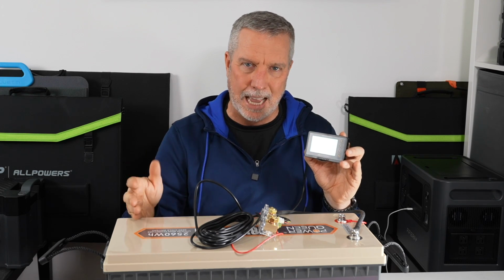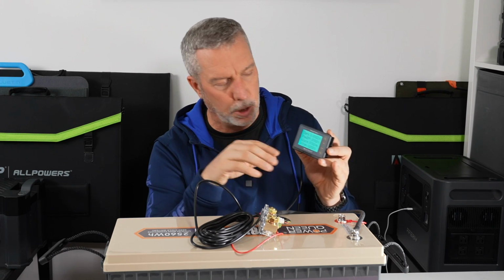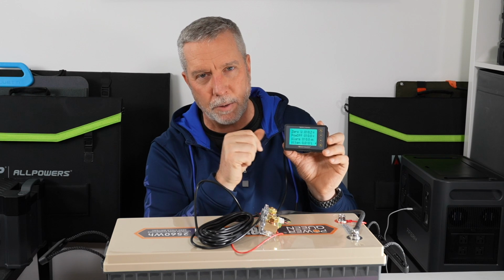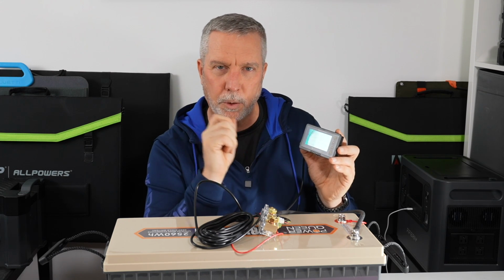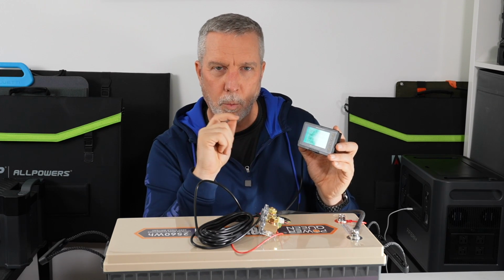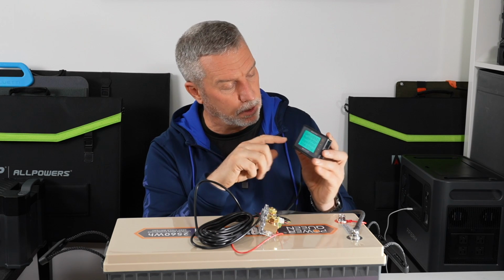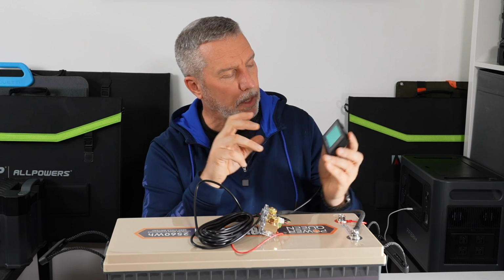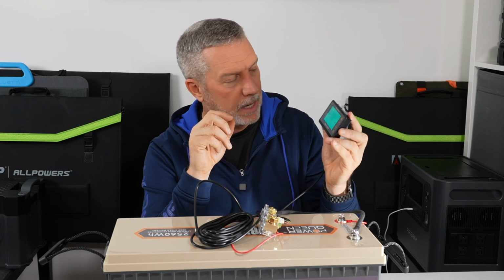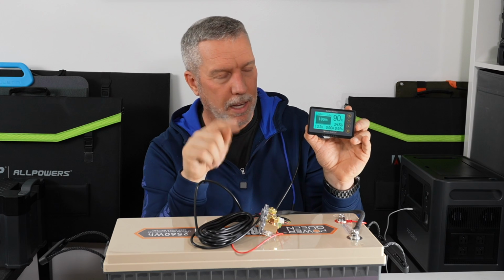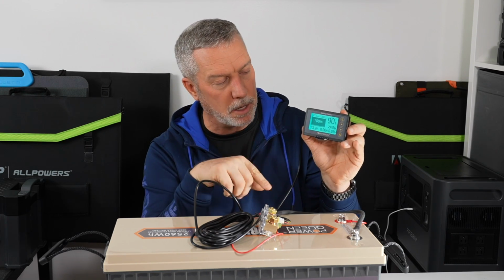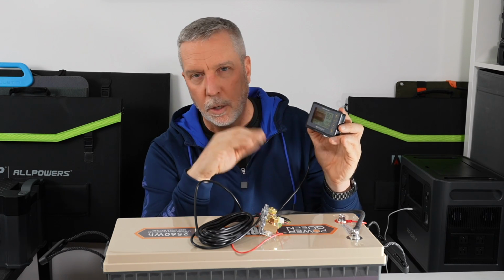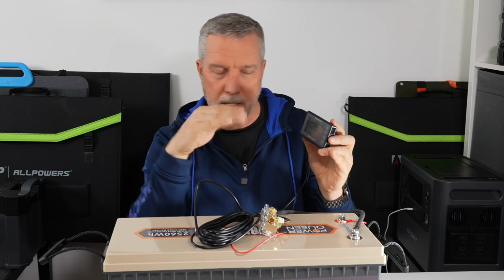When this is dead in your estimations, as low as you want it to go, you press and hold the down arrow, and that tells it that's as low as you want to go for it to say 0% on the screen. So when you go back out to the screen, that's how it got the 90%, 180 amp hours, because I set it to 200 amp hours in the menu, and I set what the zero threshold is, and it does the math for you.